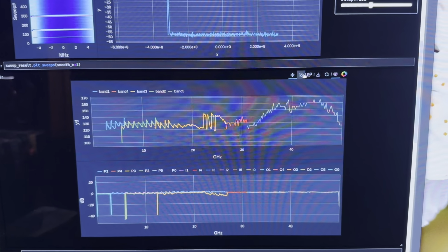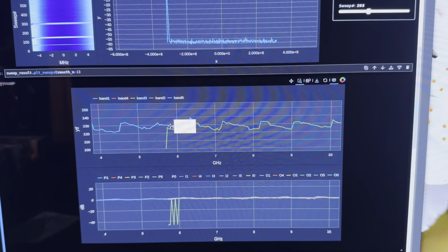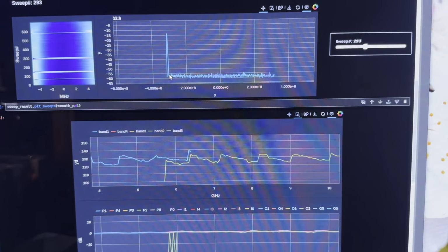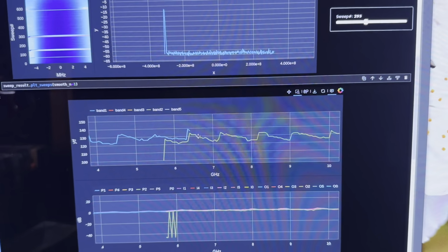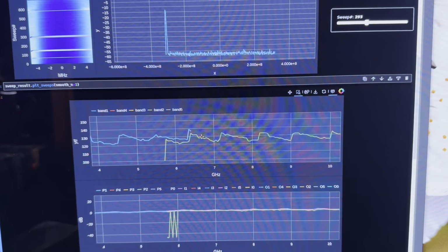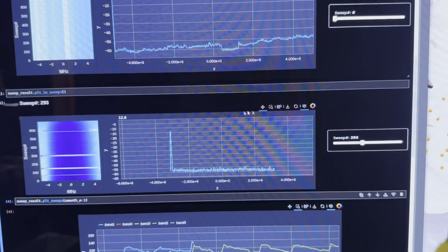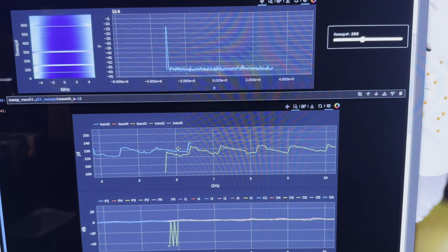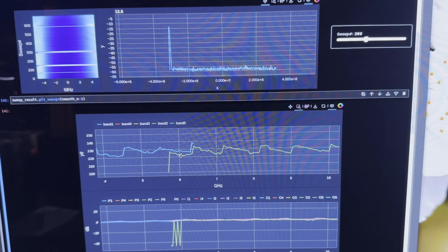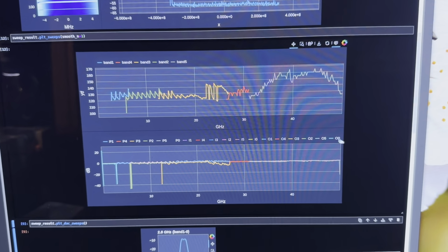But what it does do is, when we have a situation with overlapping bands, normally the spectrum analyzer likes to default to the lower band, but if we include some extra span above the peak that we're looking for, we can exceed that overlap range, and we can force it to use a higher band instead. So that's just a little trick that we use to disambiguate between one band and the other band when both bands could potentially cover the same frequency range.